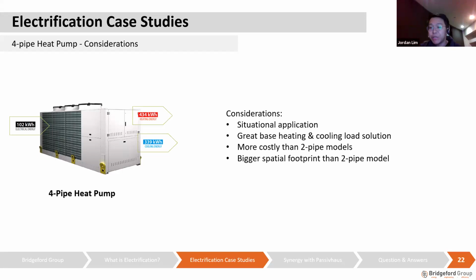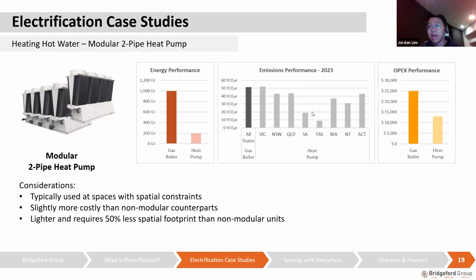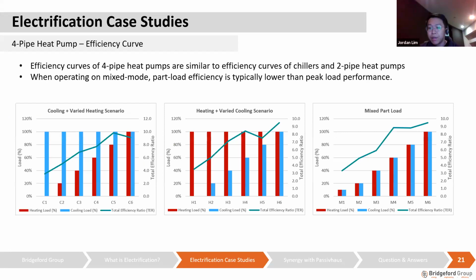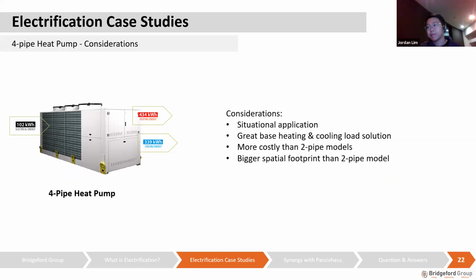I don't have the metrics, like all these graphs here, for a 4-pipe heat pump. The reason is that the performance of 4-pipe heat pumps differs for different applications. It is very situational, depending on how much heating or how much cooling is needed. So I don't think it would be fair for me to just make up a scenario and demonstrate it to you guys. But as I just mentioned earlier, it is extremely good when you can make sure that the system is consistently running at peak heating and peak cooling capacity.